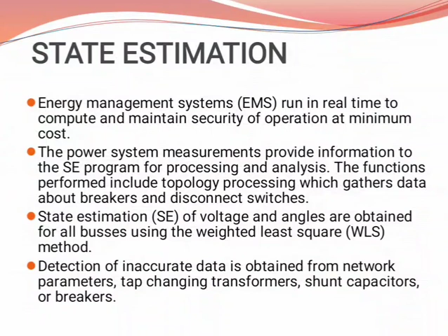Many of the algorithms in use have some problems, that is, convergence problems. Usually the convergence problems happen in traditional state estimation, which may not converge if the power system state changes faster than the SCADA data. Usually the SCADA data is slow, so for that we are now using the PMU data. The PMU data is much faster than the SCADA data. So that is the convergence problem.